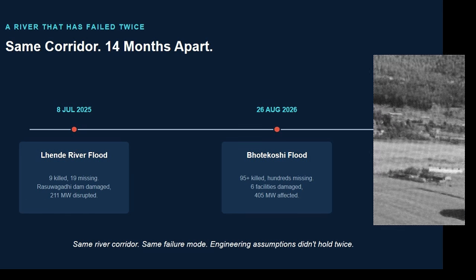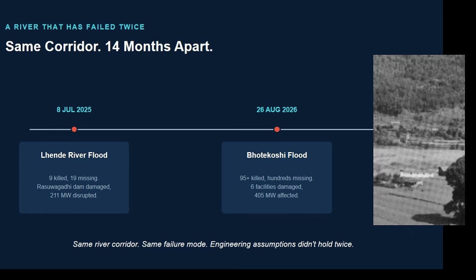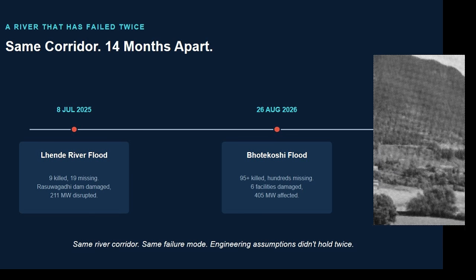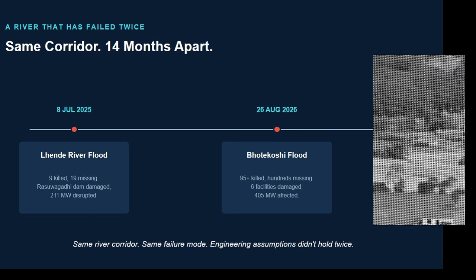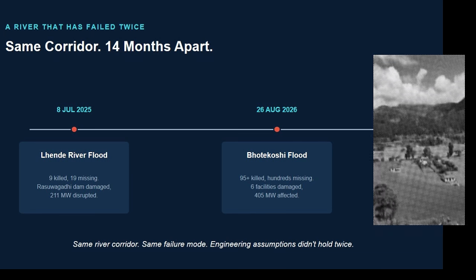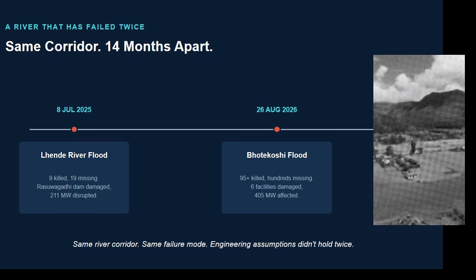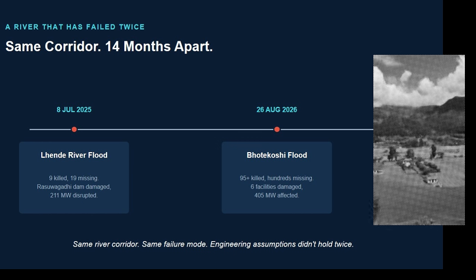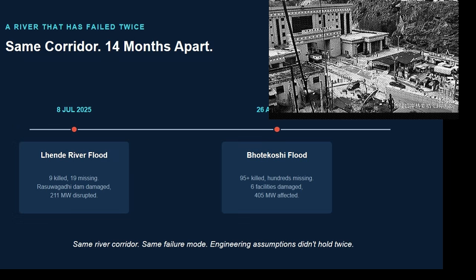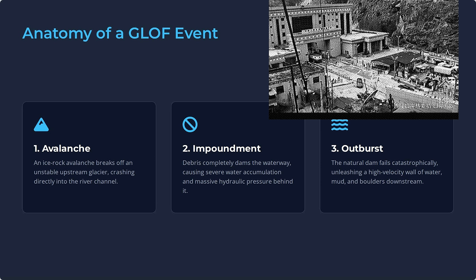Because a normal flood and a glacial outburst flood are not the same animal. A monsoon flood builds up over hours, sometimes days. Rainfall increases, river level rises gradually, and your flood forecasting model can somehow predict it. Your spillway gates are sized for that kind of gradual rise. A glacial or ice dam outburst flood is completely different. There is no rainfall warning, no gradual rise. One moment the river is normal, the next moment a wall of water, ice, and debris arrives with almost no warning time. We are talking minutes, not hours. That means the flood design assumptions used for a 100-year flood or design flood level often don't even apply here, because this is not a rainfall event. It's a sudden mass release event from a glacier or blocked river channel.